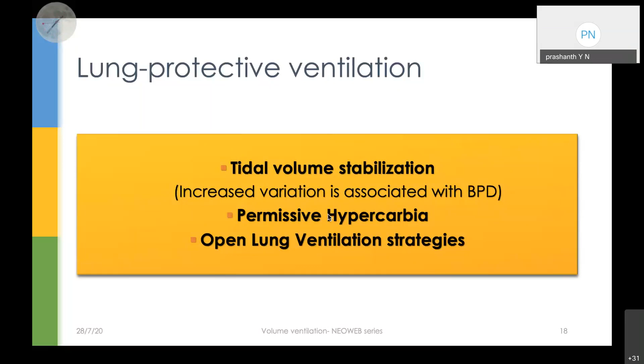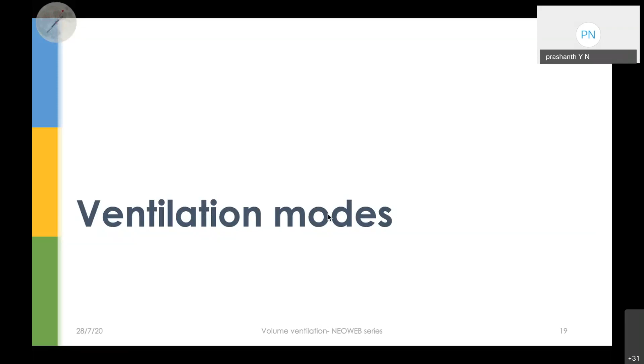So with this background, let us get into the ventilation modes. Most of us were using pressure controlled ventilation, yes or no? Most of us would use SIPPV, SIMV, PC plus PSV. All these were the nomenclatures which we grew up with during our residencies, right? This is also true elsewhere, because this is the most popular form of ventilation, that is the pressure controlled ventilation. Just to give you a brief, it is time cycled, pressure limited, continuous flow ventilation.